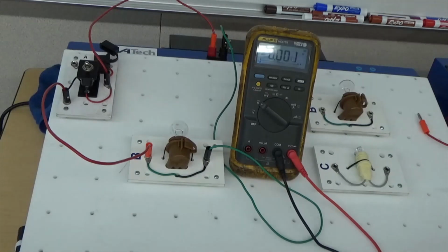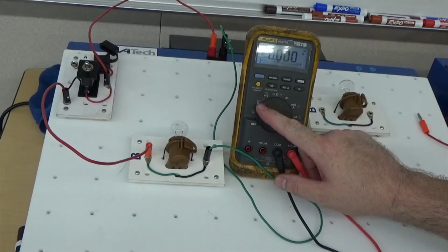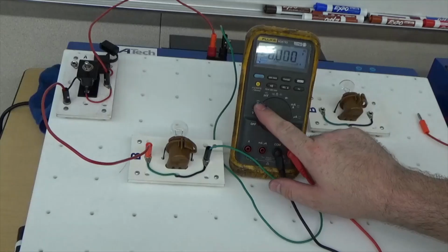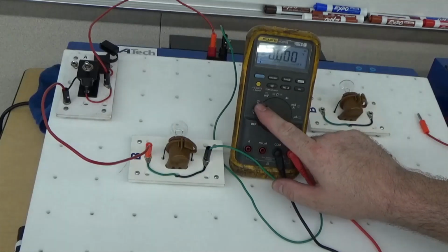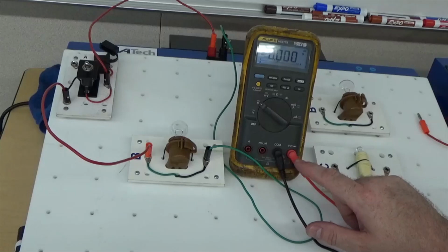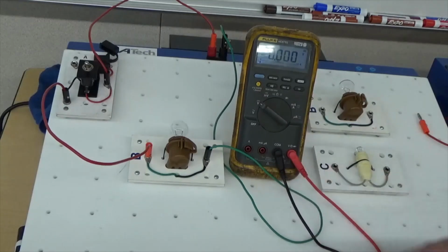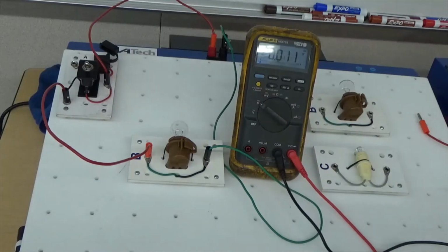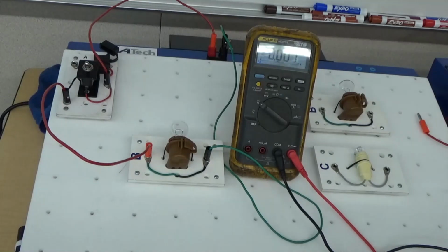When you're measuring volts, make sure that the meter is on volts, direct current. That's the straight line with the 3 dashes underneath. Black is in common, red is in volts, okay? Now these tests that you're doing, you have 2 tests you do with a voltmeter. The first test you'd use with the voltmeter is called available voltage. This means how much voltage is available, not how much voltage was consumed, how much is available. It's right there in the name, available voltage.